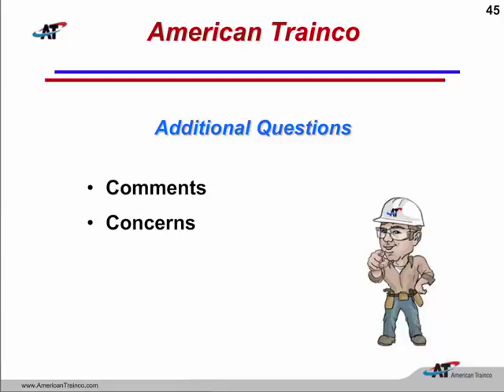Thank you. And our next question is, does normal operation apply to voltages other than 120 volt, i.e. operating a 4 kV, I think, breaker from the operating switch on the enclosure door? Sure. Normal operation of electrical equipment is going to apply to every piece of electrical equipment that we have out in the field today. So we have to take a look at, and I gave an instance of that, a 4160 volt breaker that had never even been exercised in 41 years. So normal operation is not going to be limited to any voltage.